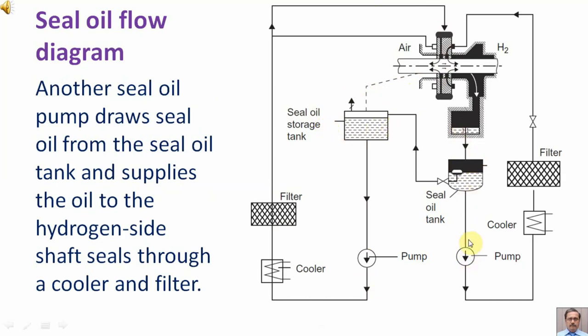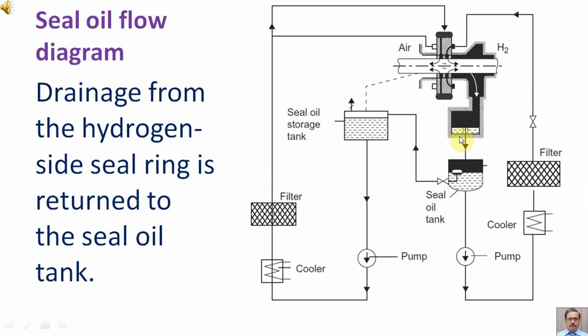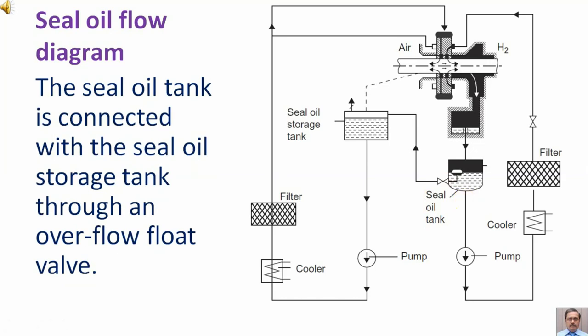Another seal oil pump draws oil from the seal oil tank and supplies oil to the hydrogen side shaft seals through a cooler and filter. Drainage from the hydrogen side seal ring is returned to the seal oil tank.